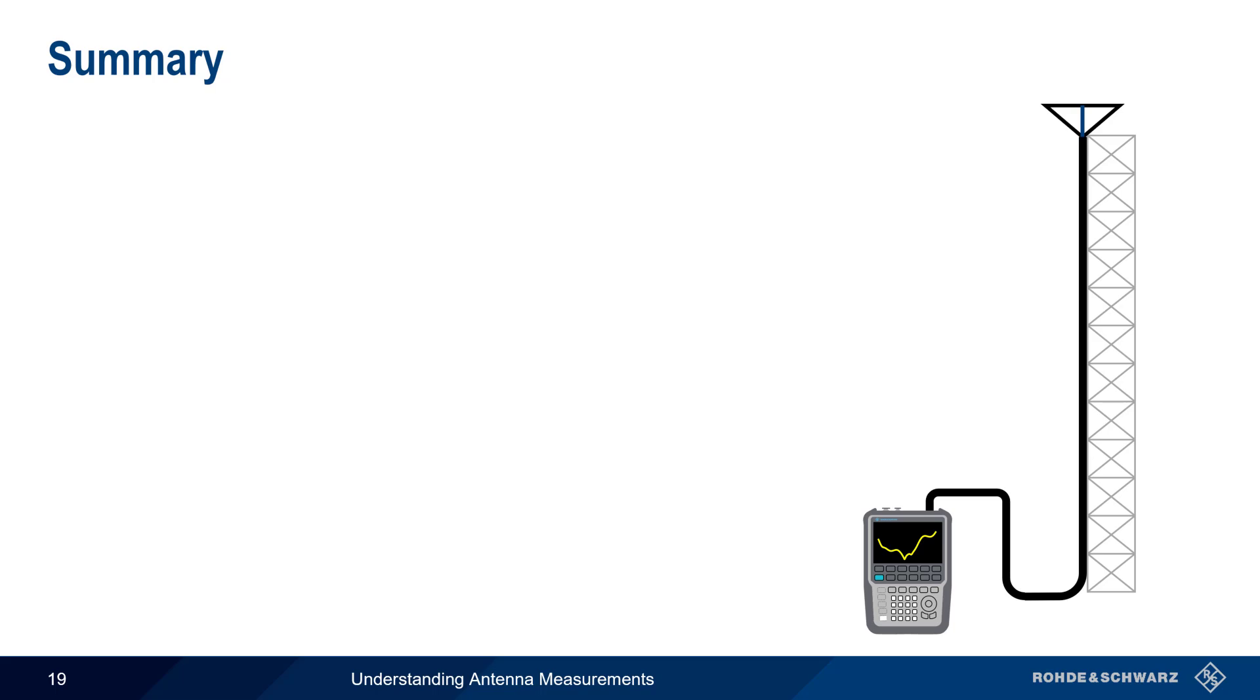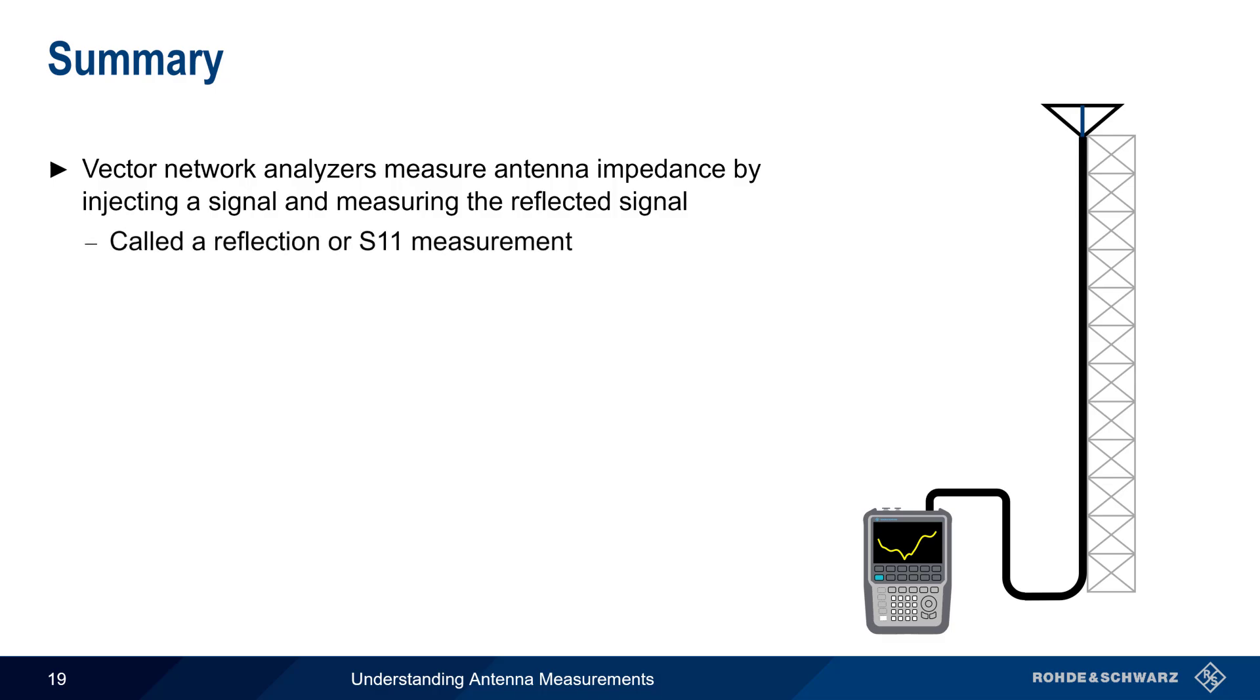Let's end with a brief summary. Vector network analyzers or VNAs can be used to measure antenna impedance by injecting a signal into the antenna or feed line, and then measuring the reflected signal. This is referred to as a reflection or S11 measurement, and is normally performed over a range of frequencies.